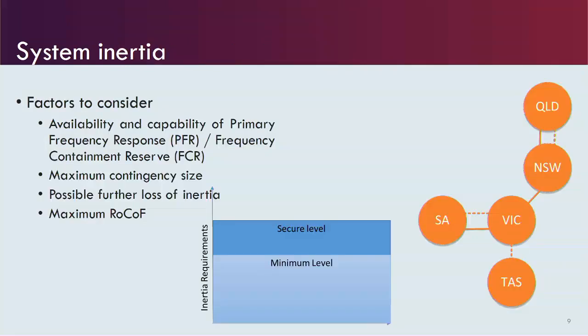One of the other major impacts that we have, which is not fully exploited yet but will hopefully be exploited in the near term, is around managing low inertia scenarios. In the power system we have a lot of asynchronous generation which is displacing synchronous generation. Asynchronous generation doesn't provide any inertial support to the NEM. Synchronous generation does. The consequence of this is that we can end up with faster rates of change from a power system event, which require faster frequency response.